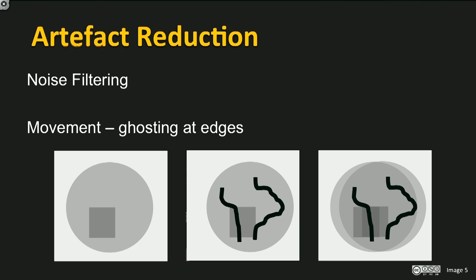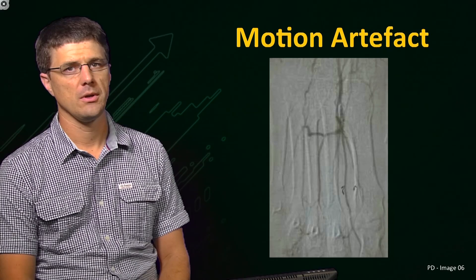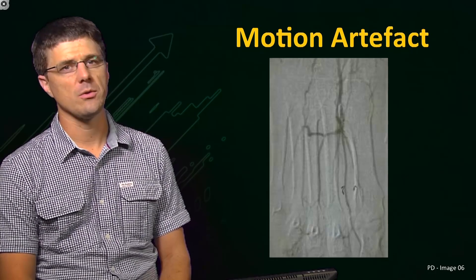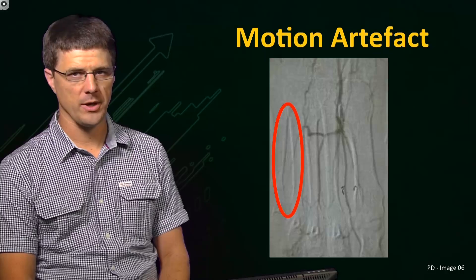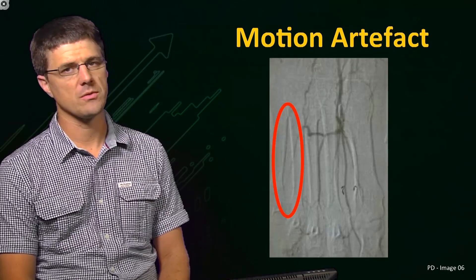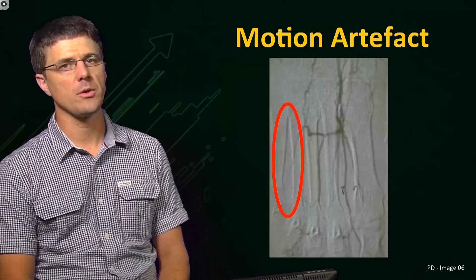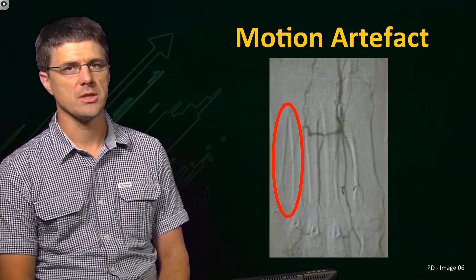A common problem in DSA is when a patient moves between the initial mask image and the following opacification image. This will result in the mask and opacification images being out of alignment. When this happens, a halo-type artefact will be seen on the resulting subtraction images, due to misregistration of the background structures. We will now see this effect in a real example. Here we can see the halo effect in the upper bones of the hand. There are a few methods to correct this artefact, including automated image registration or pixel shifting. However, a more pragmatic approach is to simply reacquire a new mask image in the new orientation.